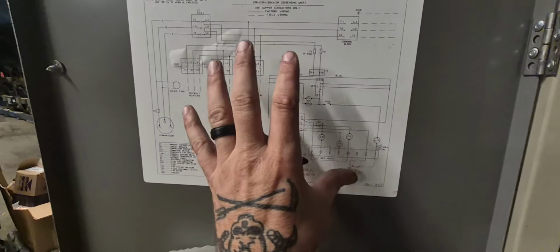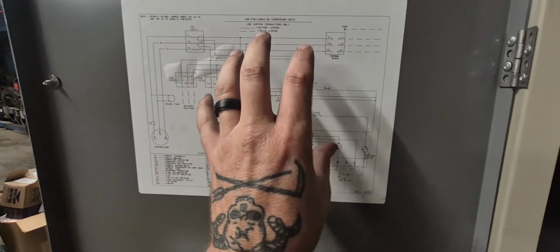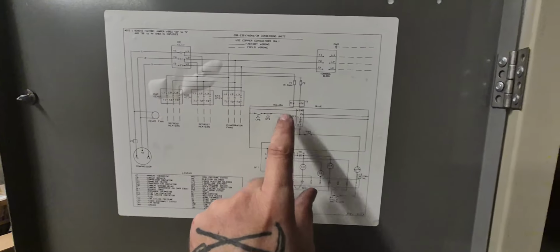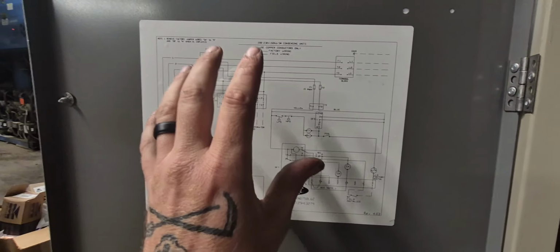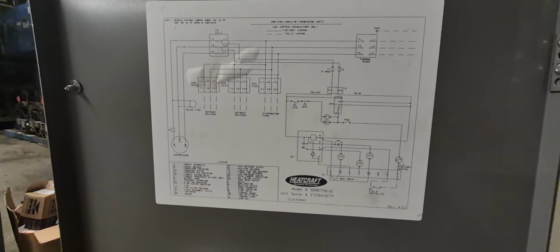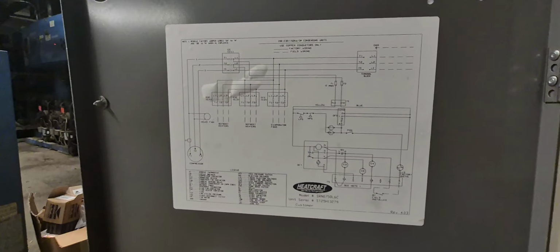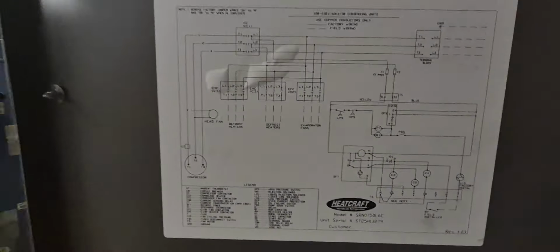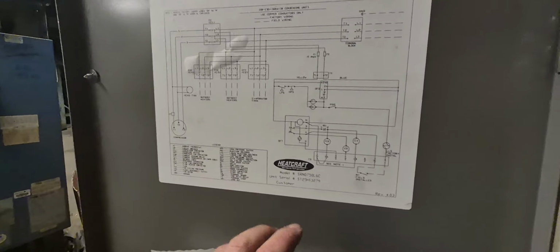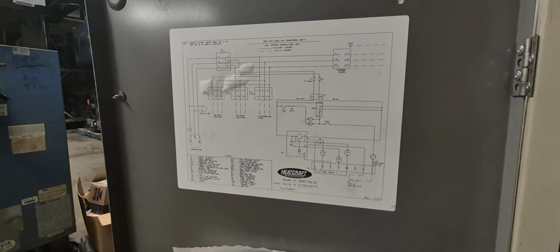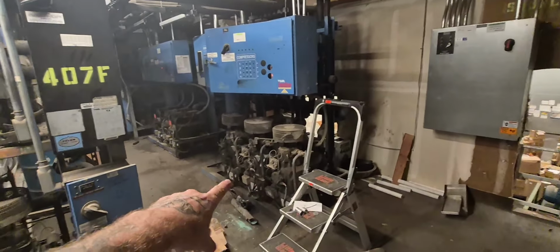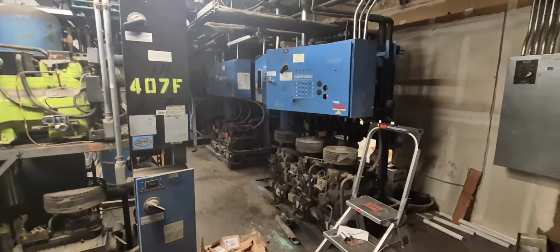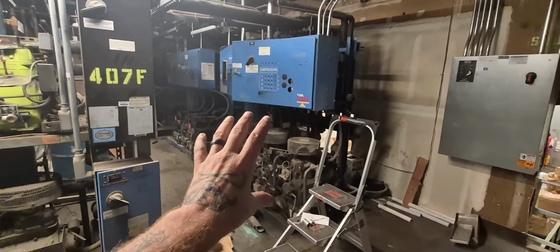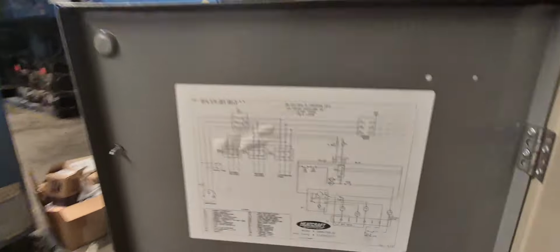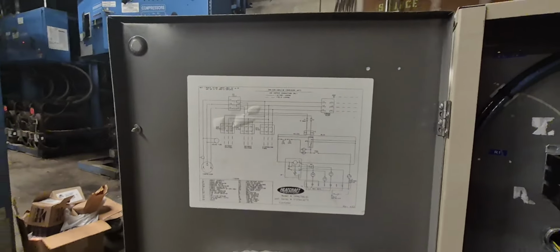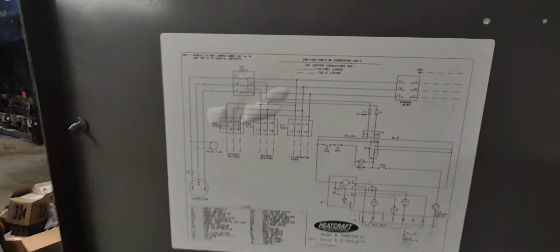If you're in service, especially service, you need to get to know these. These will help you so much in diagnosing electrical issues, because as everyone knows in refrigeration, or probably HVAC in general, the majority of what we do is electrically related. Every now and then we'll have a leak on the discharge line, or a leak at a case, every now and then we'll work on the refrigerant circuit, but the majority of what we're doing is this electrical circuit. There's so many more electrical failures than there are refrigerant failures.